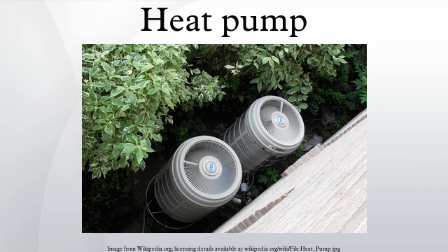Ground source heat pumps work in the same way as air source heat pumps, but exchange heat with the ground via water pumped through pipes in the ground. Ground source heat pumps are more simple and therefore more reliable than air source heat pumps as they do not need fan or defrosting systems and can be housed inside. Although a ground heat exchanger requires a higher initial capital cost, the annual running costs are lower, because well-designed ground source heat pump systems operate more efficiently.